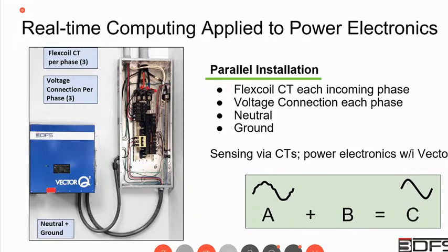It is installed in parallel. There are 3 flex coil transformers — this image is slightly out of date, my apologies; these are shown as split core, but now we use flex coil current transformers on the incoming phases. There is a voltage connection at the breaker on each phase, and ground and neutral are wired. That's the installation — it's fully in parallel.